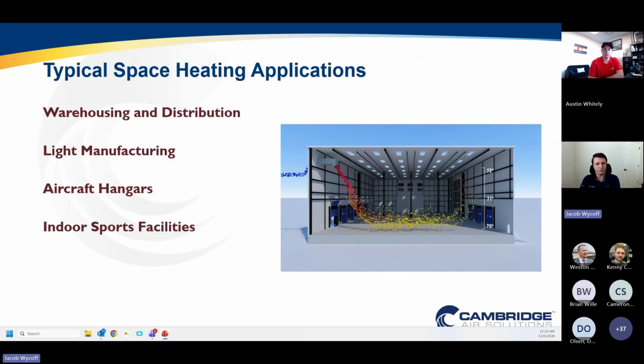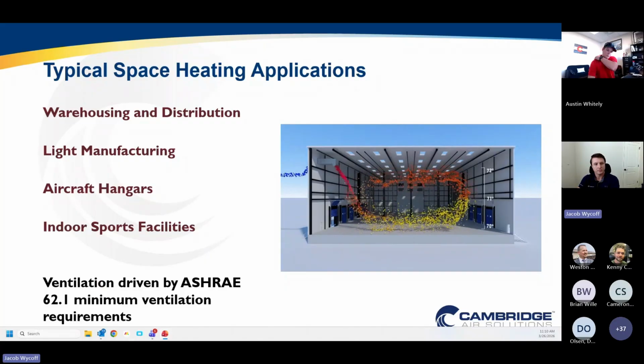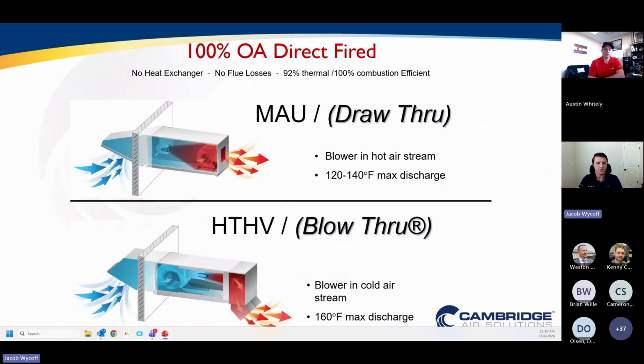Moving on to our next application would be space heating applications. These would be spaces like warehousing and distribution facilities, light manufacturing facilities, aircraft hangars, indoor sports facilities. What all of these facilities have in common is that they have very little ventilation that's actually required. And actually the need of the space and this unit equipment selection is going to be driven by the amount of heat required. So we're selecting the unit based off heating the space. And then as a result of providing heat to the space, the unit's also able to meet the ASHRAE 62.1 minimum ventilation requirements. So we actually have a different product offering for these applications.